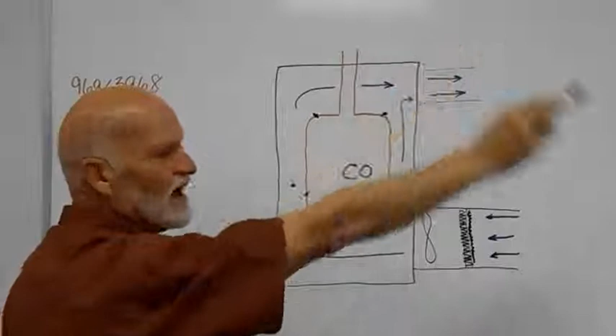The problem is that they build these things with a joint. Well, it looks like this. These are called rolled seams in the stainless steel. These are designed to flex a little bit because when the heat exchanger gets hot, it needs to expand, and when the thermostat says that's enough, it shuts down and it cools back down.